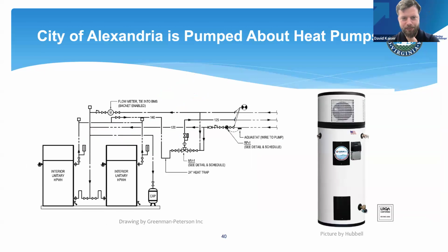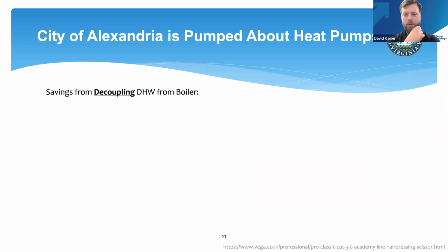All right, next, please. And so this is what we're going to put in place. We're putting heat pump hot water heaters in there. So it's in the boiler room with the space heating boiler, so there's some residual heat coming off of that. And these heat pump hot water heaters are going to be able to extract some of that energy from the boiler.